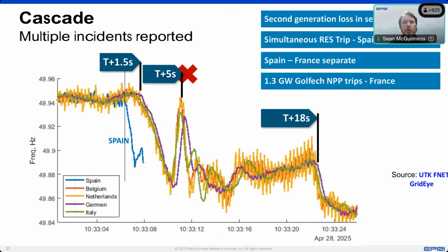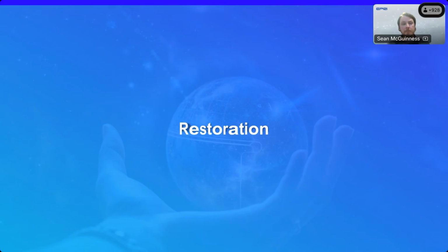We do know from the press conference, though, that the system was in a system black state at t equals 5 seconds. So it was very rapidly evolving. There was no way for the system operator to be able to actively respond in that 5-second interval. It was far beyond that. So moving on from the key facts that we know about the actual disturbance event itself.